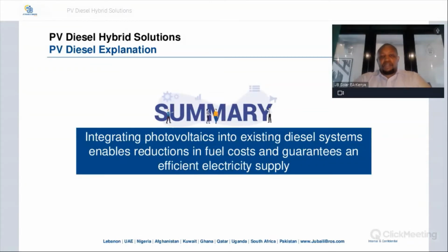So in summary, we have generator and grid protection, where you want to make sure that you're not causing damage to your generator, as well as not feeding back into the grid. And you're integrating the PV solar system into your existing DG to reduce fuel costs and also guarantee constant and efficient electricity supply.